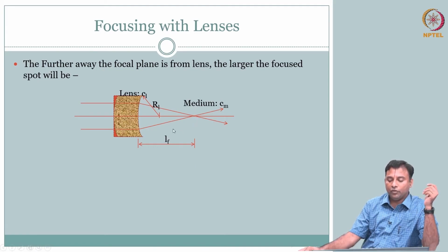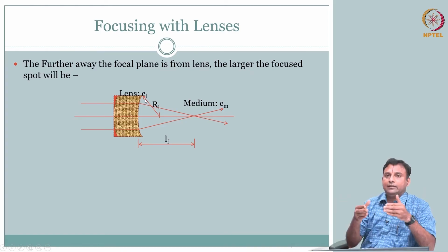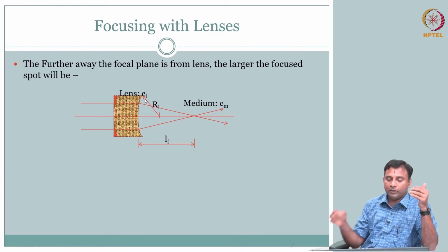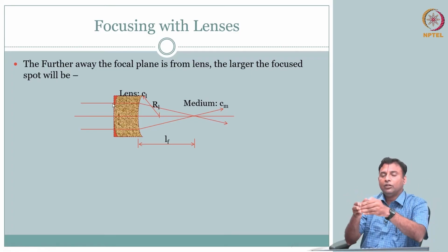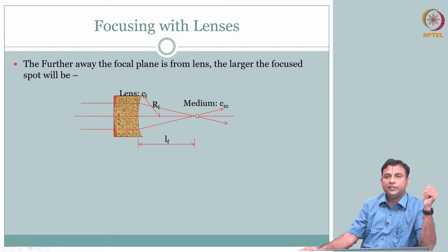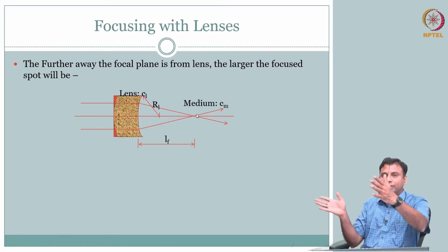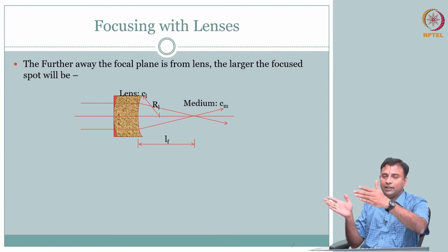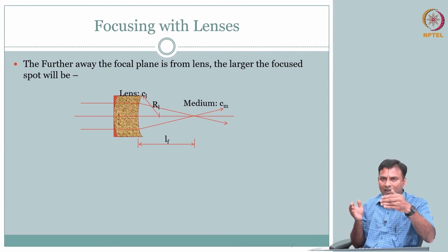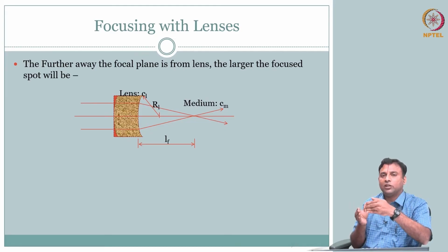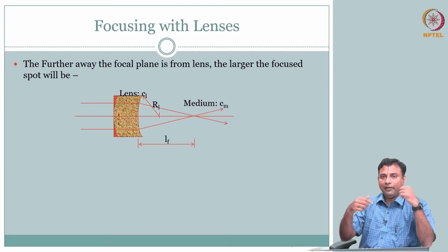So the length of focus is the location Z at which this lens is going to help focus the beam. So all the acoustic pressure coming from the surface of the transducer, all of them are going to be focused to a smaller region here. So it will become the narrowest. The divergence we talked about, instead of divergence, before it starts to diverge, I want to make it as small a region as possible in the imaging plane.